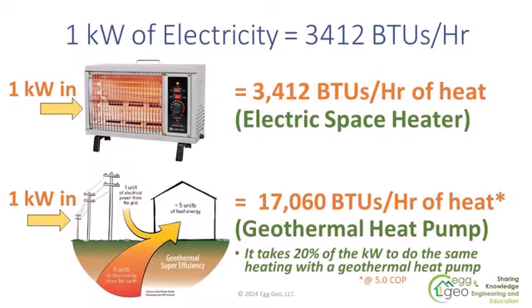However, if you take that same kilowatt of energy and you give it to a geothermal heat pump that has a good heat source, that 1 kilowatt of energy is not going to be burned to make heat. It's going to run a motor. It's going to run a compressor. It's going to run a fan. It's going to run a pump. And for 1 kilowatt of energy, that motor, fan, and pump are going to pump 4 more units of energy from the ground and give you a grand total of 5 units of energy in the space, for a grand total of 17,060 BTUs at a 5.0 COP. So in this instance, it takes 20% of the electricity to deliver energy as compared to direct electric resistance heating. And that's the beauty of a heat pump.